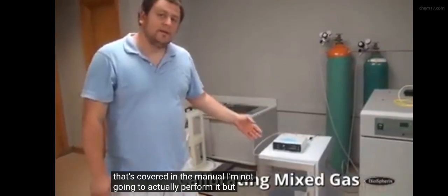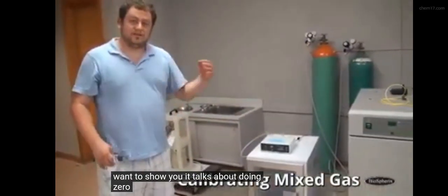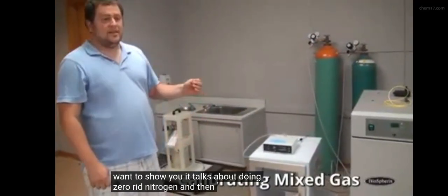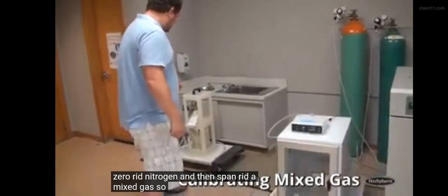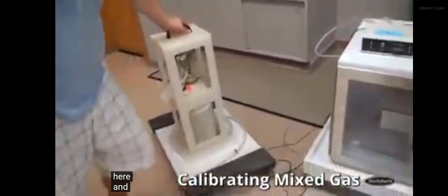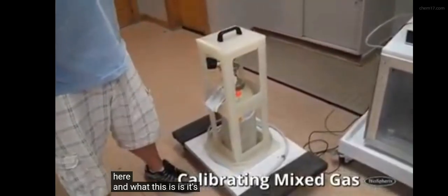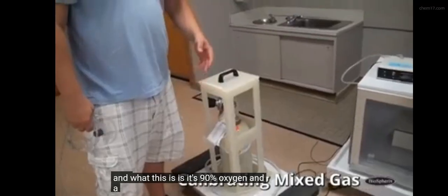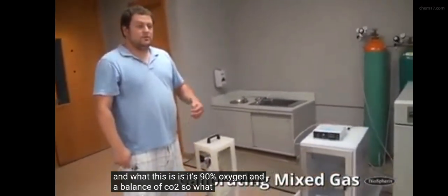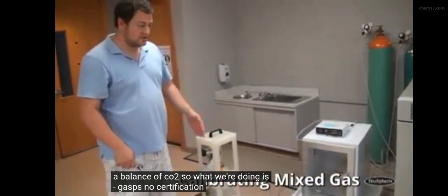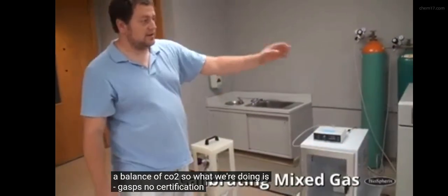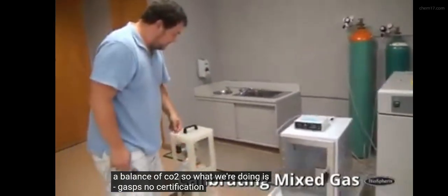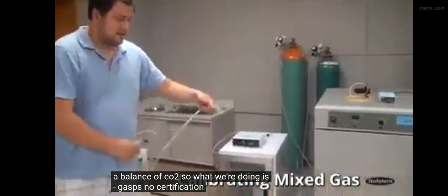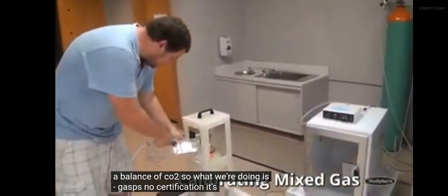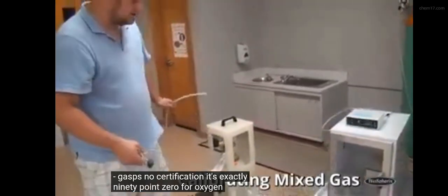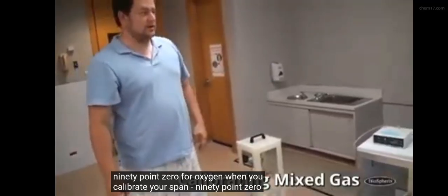I'm not going to actually perform it, but I do want to show you. It talks about doing zero with nitrogen and then span with a mixed gas. So I brought up our mixed gas tank here, and what this is, it's 90% oxygen and a balance of CO2. So what we're doing is 2 gas known certified levels. So you do your zero just like we did with the P110, and then you would hook up your mix tank to the controller, and it would be whatever the tag says. In this case, it's exactly 90.0 for oxygen, and you would calibrate your span to 90.0.